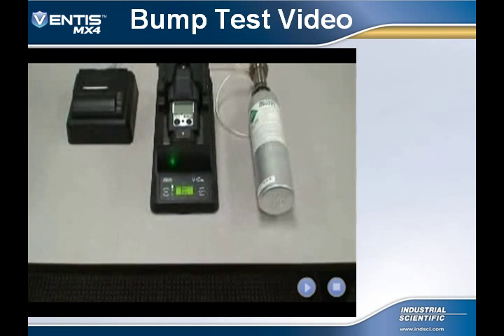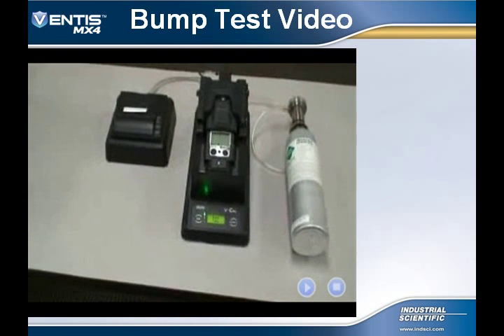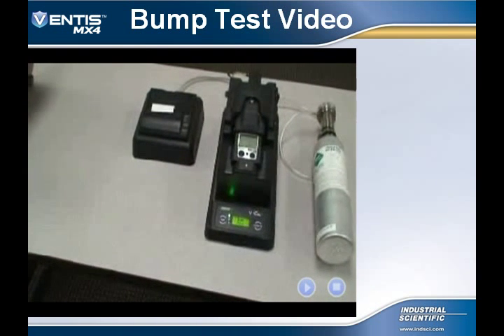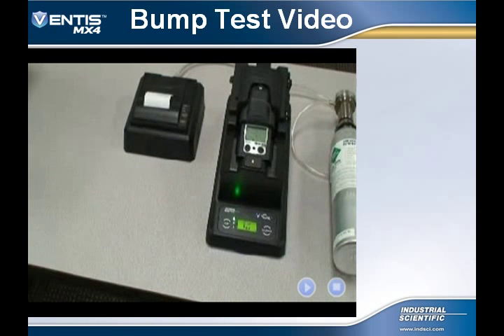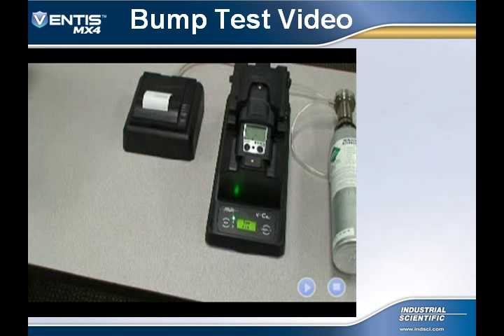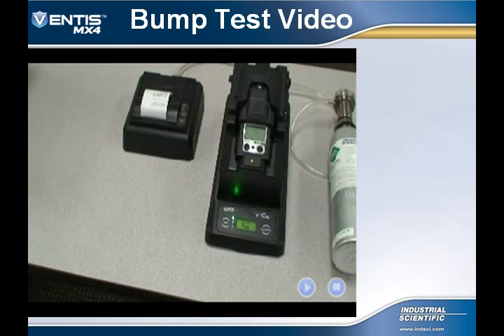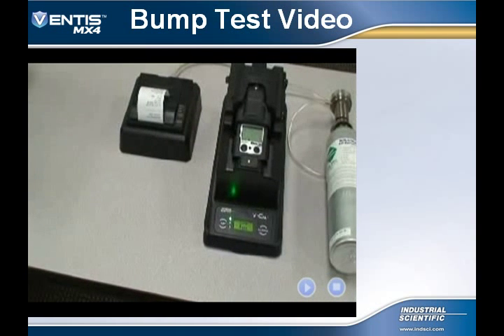Upon completion of the last sensor, a successful bump test will display a green LED with the VCal's display showing pass. If any of the sensors failed their bump test, then the red LED will be illuminated with the VCal's display showing failed. At that time, a full calibration of the instrument will need to be accomplished. A printer may also be connected to the VCal to print a hard copy of the results of the bump test.